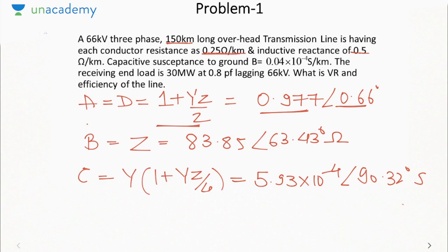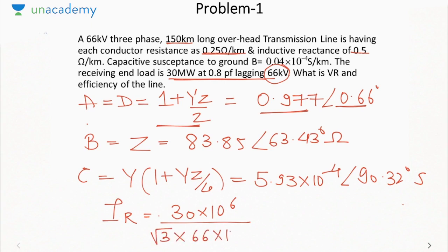Now, to calculate the efficiency, we need the sending end power and the receiving end power. For sending end power, we need sending end voltage and sending end current. For those, we need VR and IR. So VR is this one, but I do not know IR. As I told you, whenever you see a loading, the first thing that must come to mind is current. So IR will be 30 into 10 raised to the power 6 divided by root 3 into 66 kilovolt into 0.8 power factor lagging. This comes out to be 328.03 ampere.